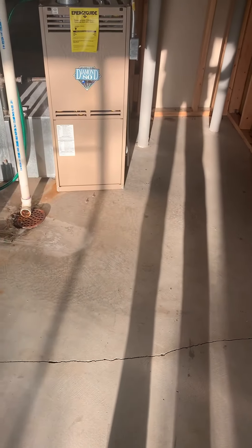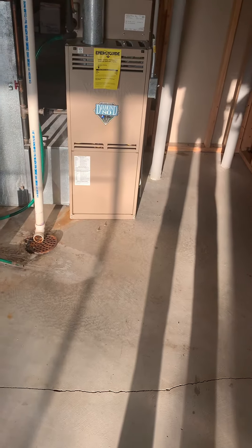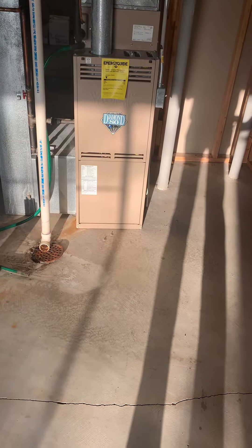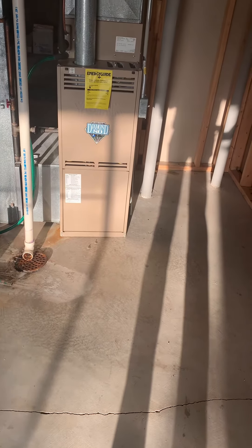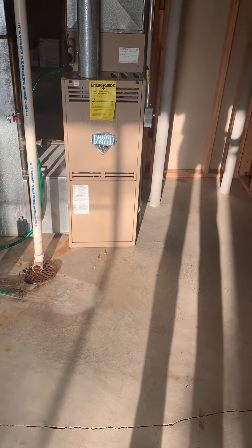Taking a look at a York 80,000 BTU furnace. Due to some water damage from the second floor unit down to the board, this unit isn't running the way it's supposed to be. It's actually been wired and just to bring on the blower with the heating, but will not work for cooling. So we've got some damage here.